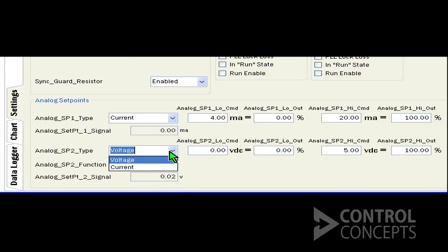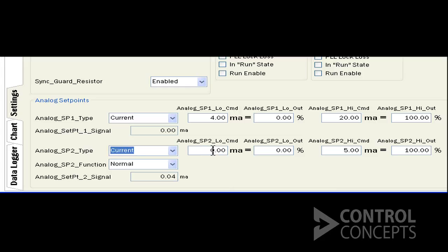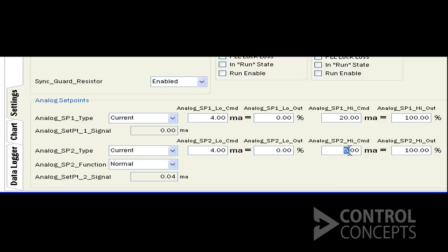Now first we'll change voltage to current as you see here. For our demonstration we're going to use 4 to 20 milliamps as our input command signal, so enter 4 as the off state signal and 20 as the full on signal. We are now configured for 4 to 20 milliamp input.